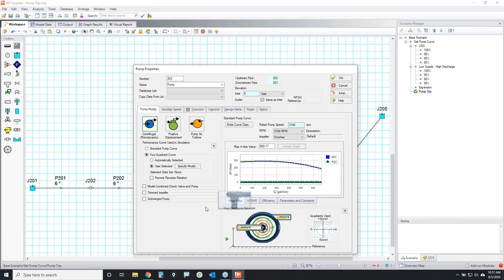So now when I click on this animation again, I might have reverse speed. That's when the pump spins backwards. So you can see how the orange lines indicate that the pump is not only experiencing reverse flow, but the reverse flow also makes the pump impeller spin backwards. And so that's where you need to have a data set of pump information that can match that. And that's what a 4-quadrant data curve is.